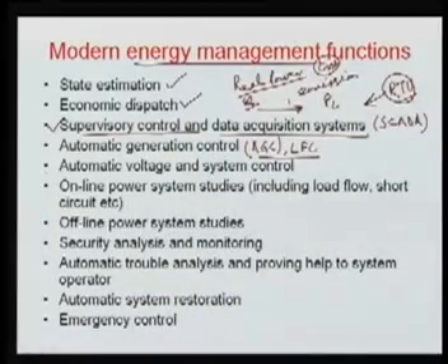Another is automatic voltage and system control, sometimes called automatic voltage regulator or automatic voltage control. In any generating power system, we have two loops. A generator is equipped with an excitation system. That excitation system controls the terminal voltage of the generator, and it also sets the reactive power output.